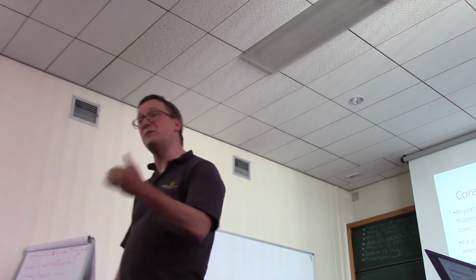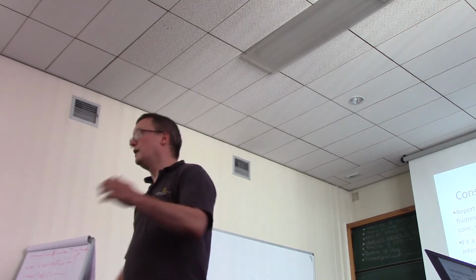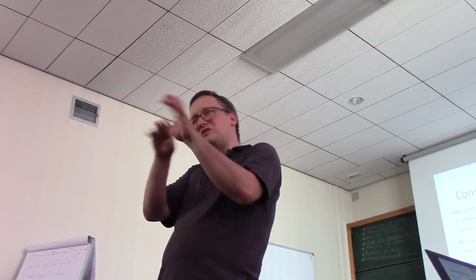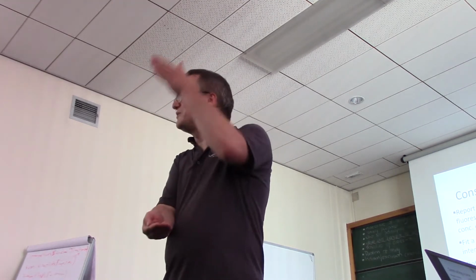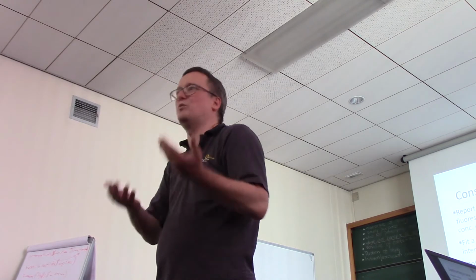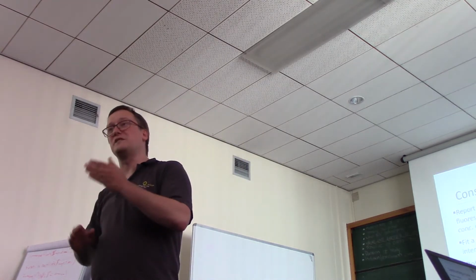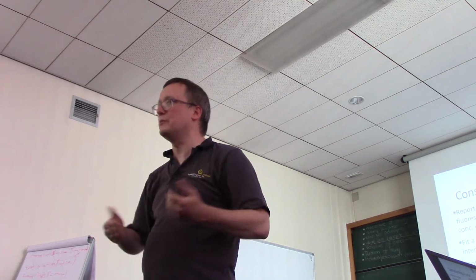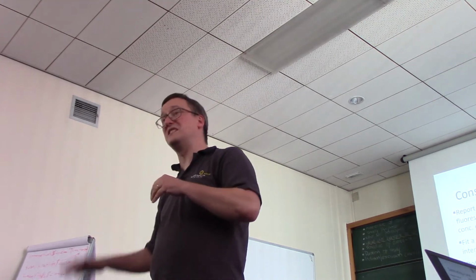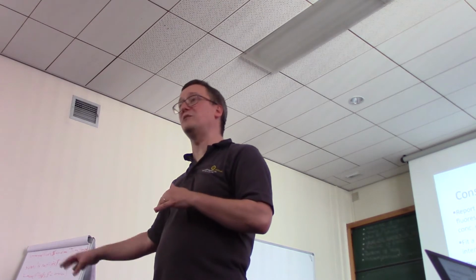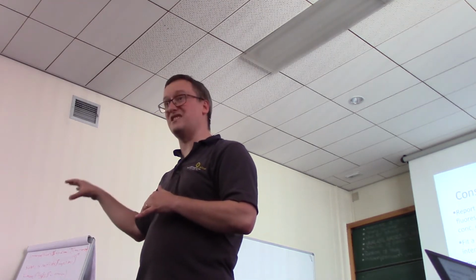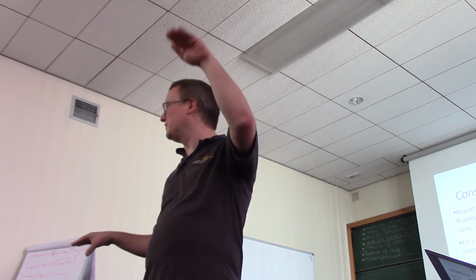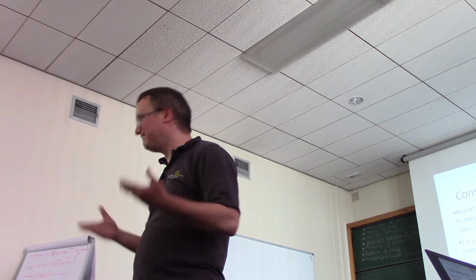So that's the same effect that you get out of a Luminex box. When you get to the very top of concentration, there's just a limit on what the maximum amount of light can be read off of this well is. And as a result, there's some maximum past which you can't push and get a sensible concentration measurement. We have some light attenuation at the bottom that's causing signal when nothing is there, and you have some amount of attenuation at the top where more sample does not lead to more light.